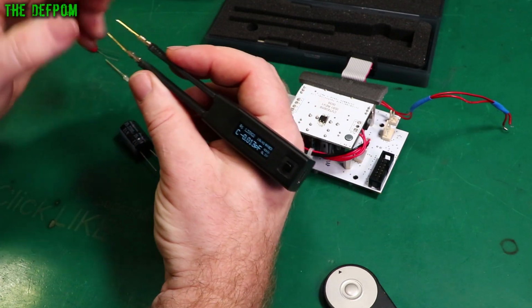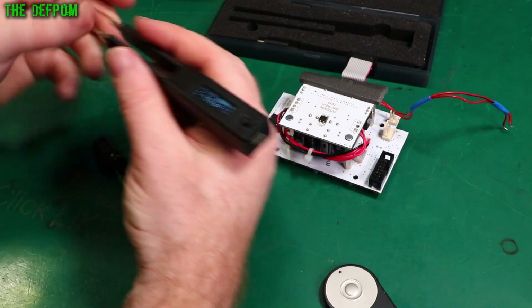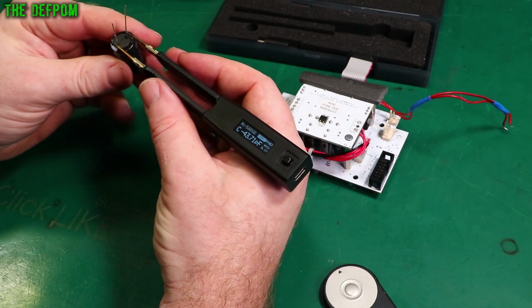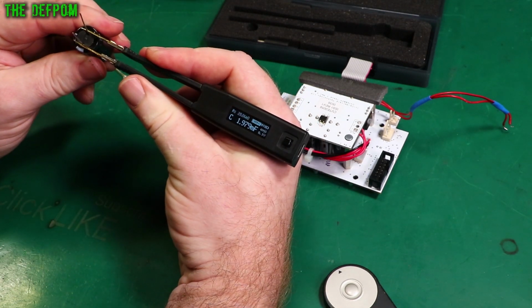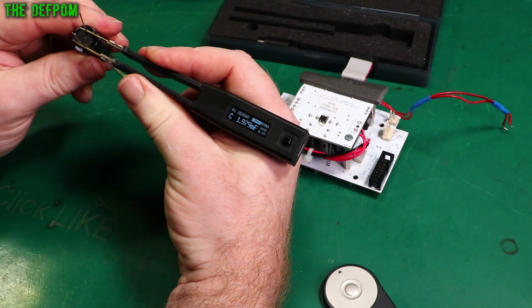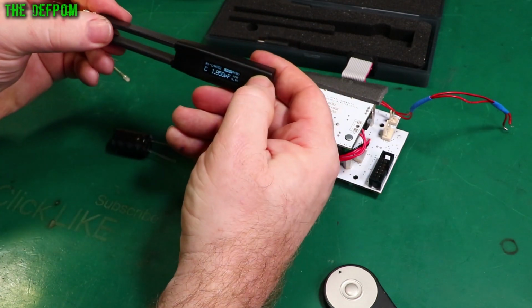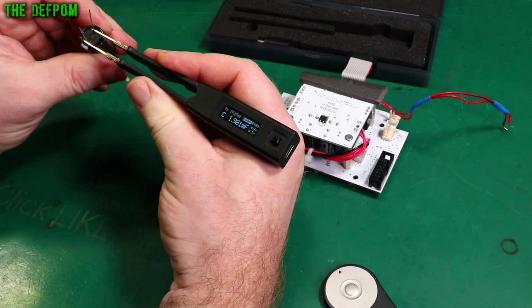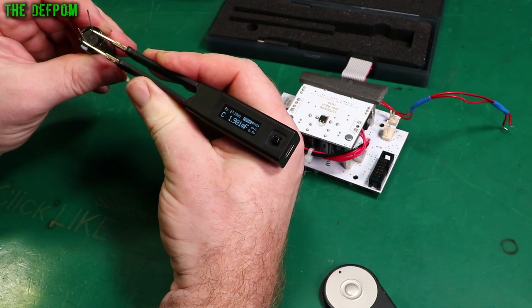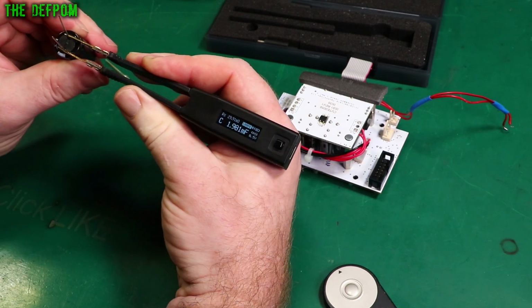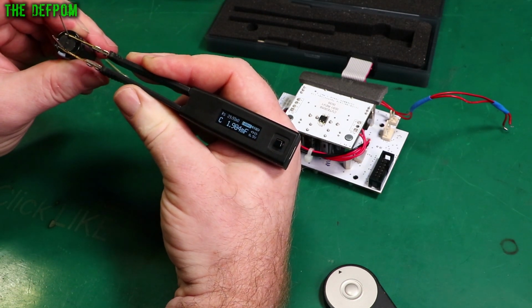That's at 10 kilohertz. Let's change the frequency. 100 hertz. Test it again. It gives the same reading. Let's increase the voltage. Half a volt. Slightly higher reading there. Bit more erratic, interestingly. Also shows series resistance of 29 milliohms.